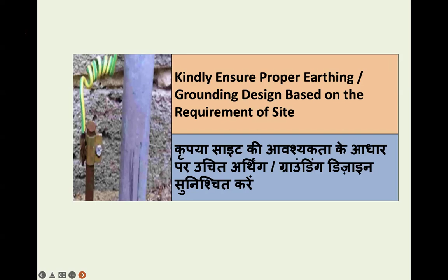Kindly ensure the proper earthing and grounding design based on the requirement at site. And always keep in mind OLOE: one location, one earthing system. When I say one location, one earthing system, I never say one electrode. I say earthing system. There may be some electrodes for your lightning protection, some for your electronic system, and some for your power system. All these systems must be interconnected. That is the meaning of OLOE. One location, one earthing system.